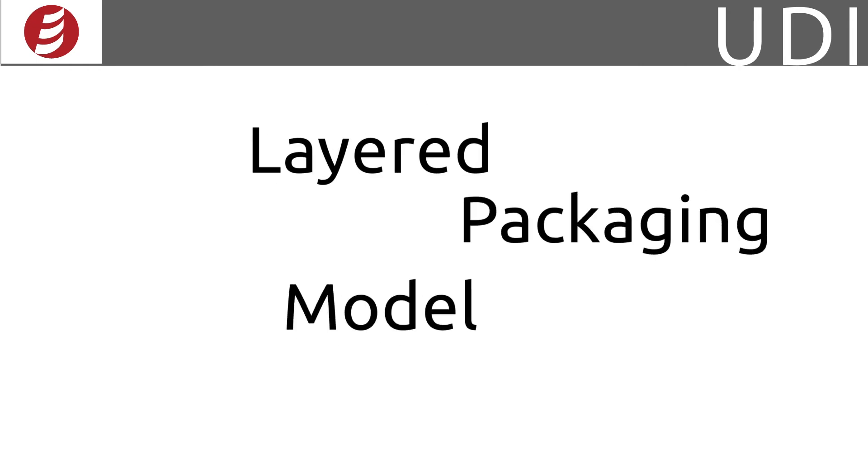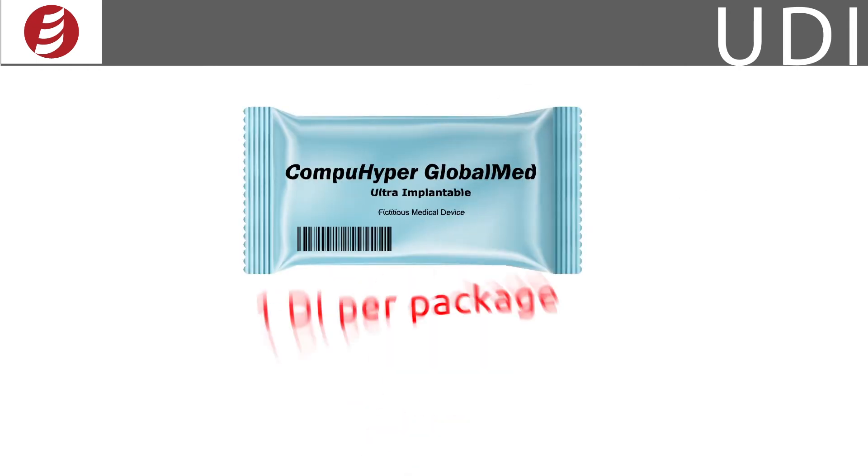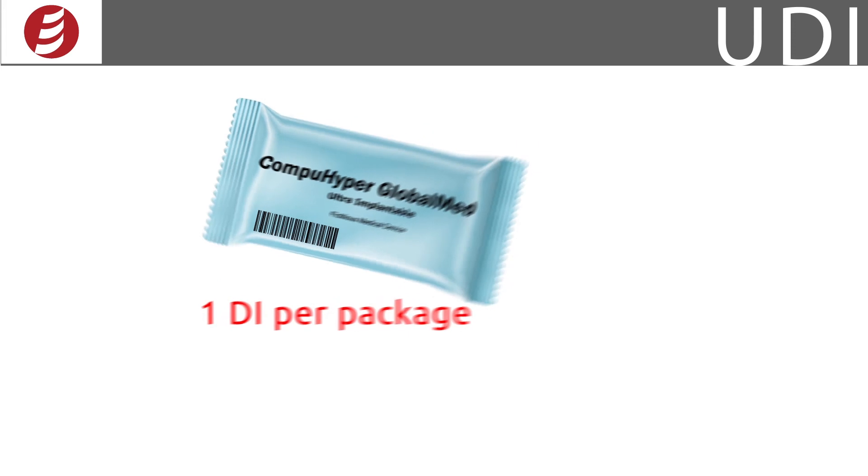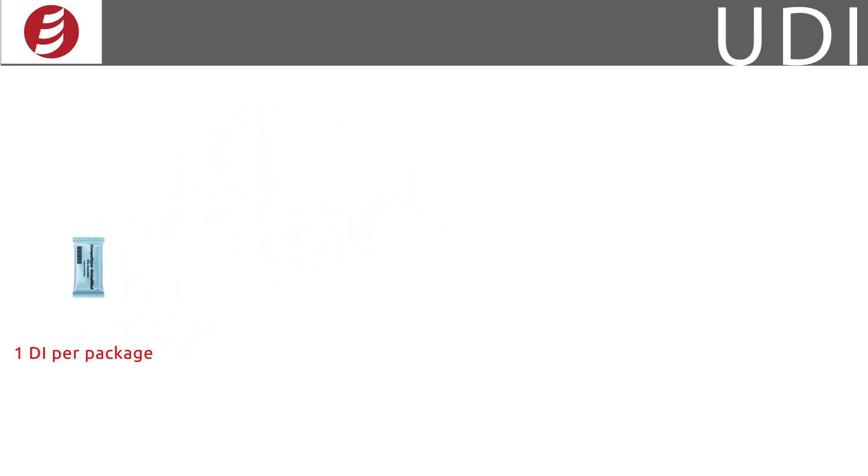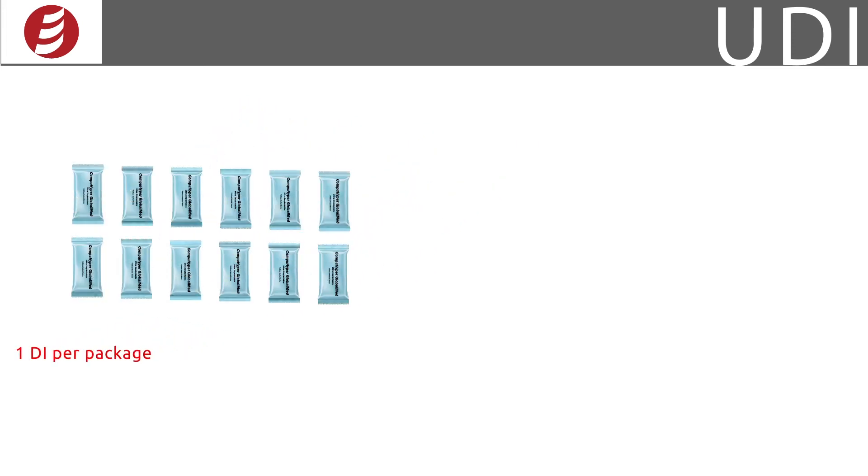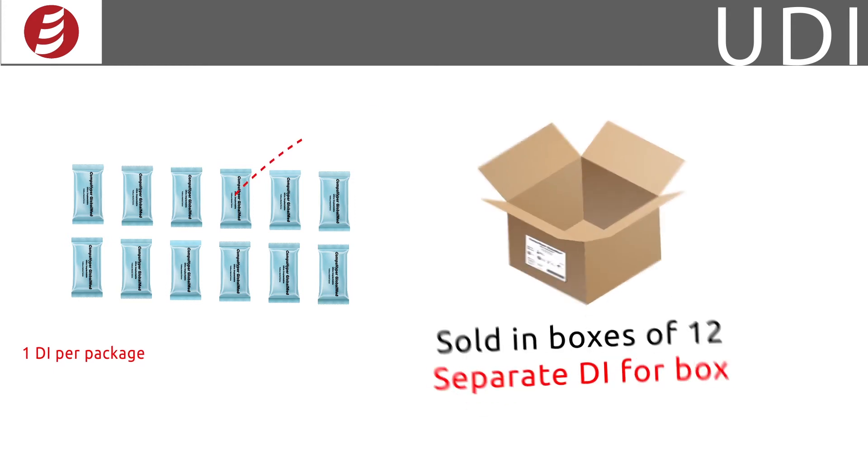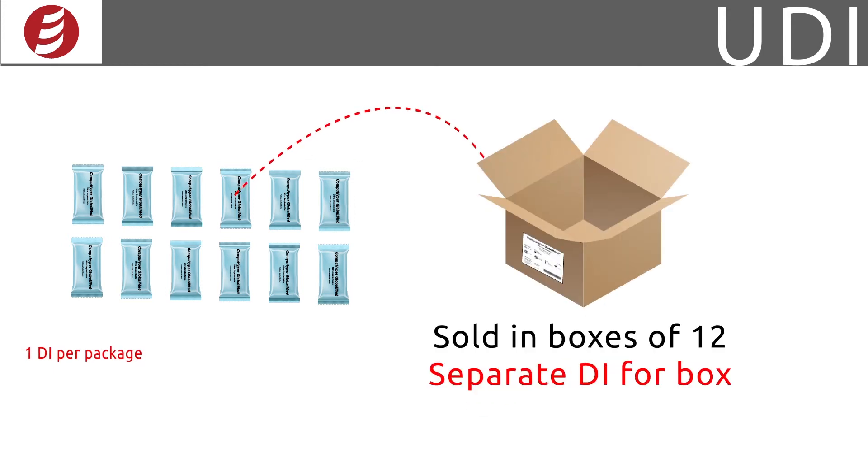Packaging follows a layered model of UDI labeling. This means if your device ships in a base package such as a wrapper, each package is assigned its own DI. If that base package is sold as a unit in a box of, say, 12, that box is assigned its own DI.